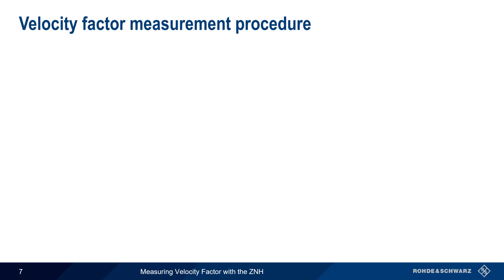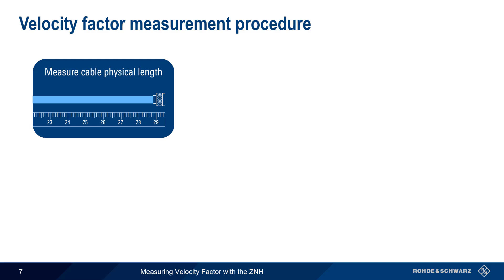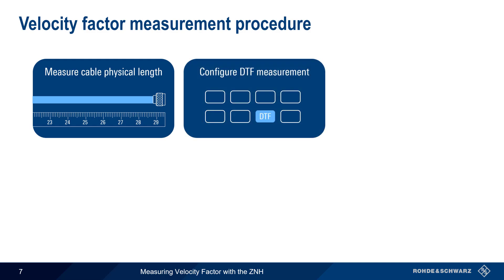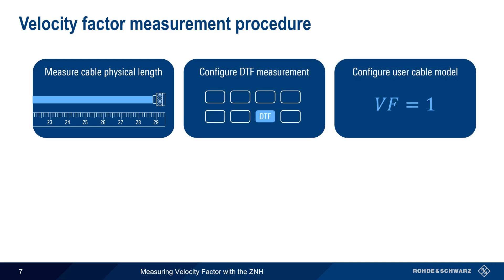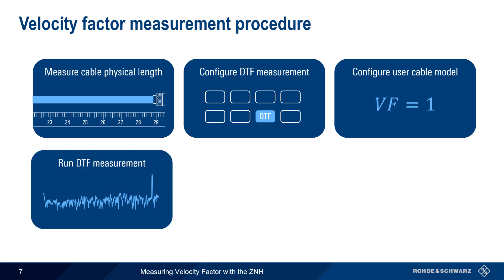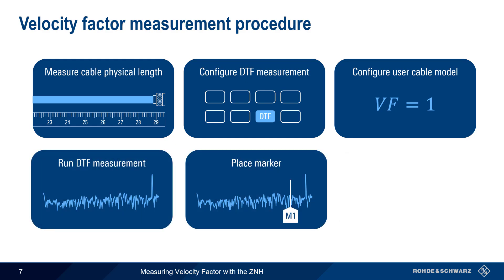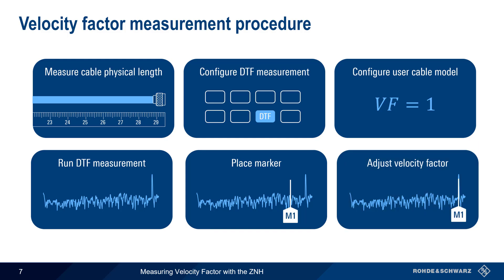The steps in our procedure, therefore, are: measuring the cable physical length, configuring the DTF measurement, creating a user cable model, running the DTF measurement, placing the marker, and adjusting velocity factor. In the remainder of this presentation, we'll provide a detailed explanation of how to perform each of these steps using the ZNH.